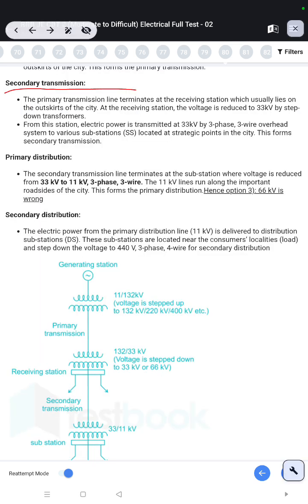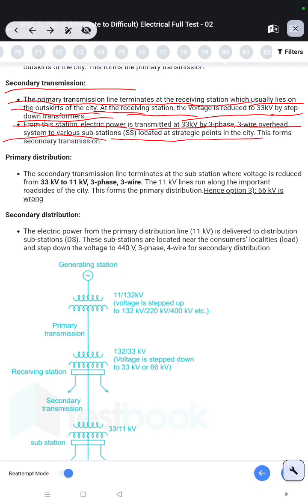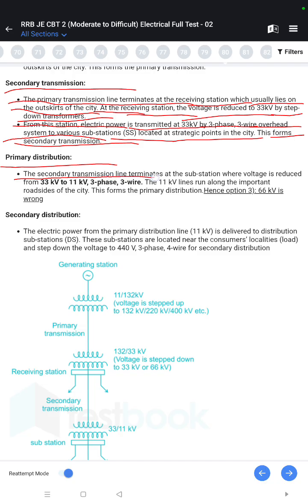Secondary transmission: the primary transmission line terminates at the receiving station, which usually lies on the outskirts of the city. At the receiving station, the voltage is reduced to 33 kilovolt by step-down transformers. From this station, electric power is transmitted at 33 kilovolt by three-phase three-wire overhead system to various substations SS located at strategic points in the city. This forms secondary transmission.